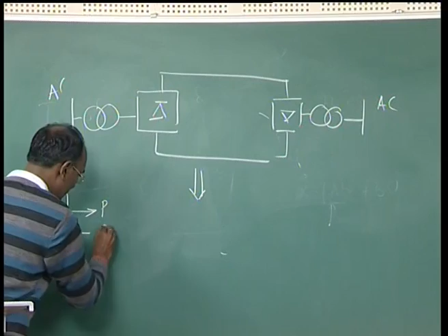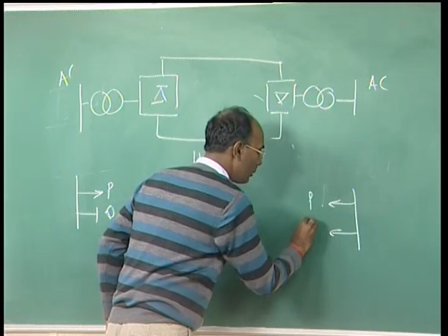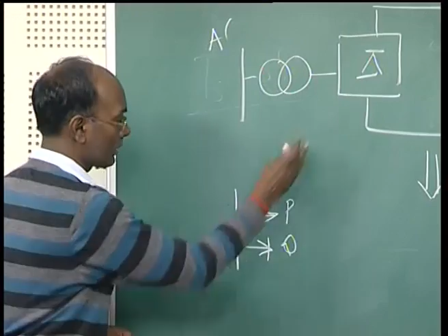We represent the P and Q at this bus, and this can be represented by P and Q here. The direction of P and Q is decided by the direction of real and reactive power flow. Mostly the reactive power is taken by the converter, so it flows in this direction, but the real power flow will be unidirectional. So it is very simple - we basically ignore detailed modeling of the DC system, only taking the AC system, and the buses where we have DC are represented just as power injections.